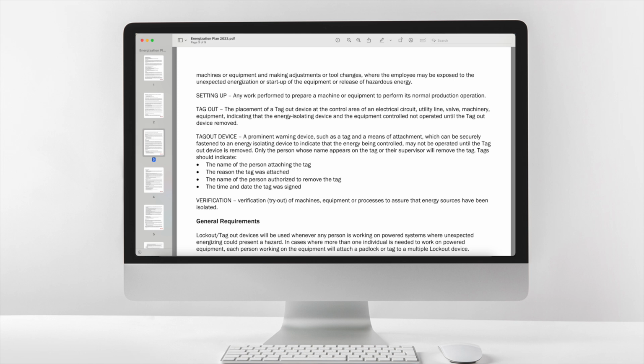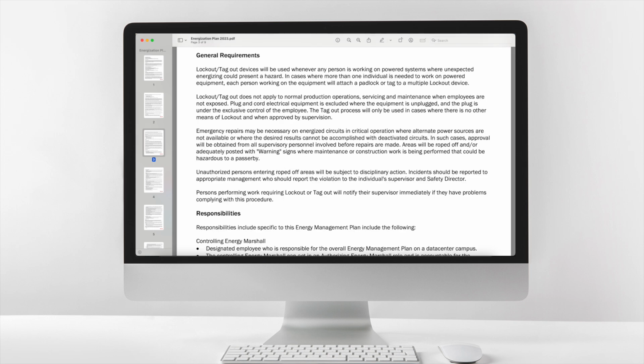General requirements. Lockout, tagout devices will be used whenever any person is working on powered systems where unexpected energizing could present a hazard. In cases where more than one individual is needed to work on powered equipment, each person working on the equipment will attach a padlock or tag to a multiple lockout device. Lockout, tagout does not apply to normal production operations, servicing and maintenance when employees are not exposed. Plug and cord electrical equipment is excluded where the equipment is unplugged, and the plug is under the exclusive control of the employee. The tagout process will only be used in cases where there is no other means of lockout and when approved by supervision.